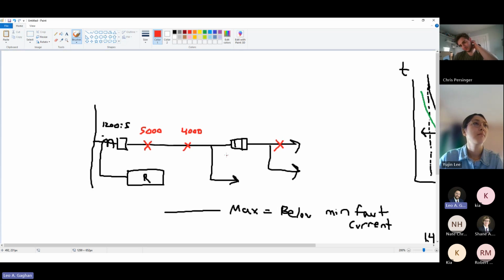So what we can do is not coordinate like we talked about before, but we can actually make this guy faster than the fuse. So when that fault happens, this device will clear that fault and the fuse will be saved. So we'll have that fast curve that's faster than the fuse. And then we can have a slow curve so that if it is a permanent fault, we can swap to that slow curve. The fuse can clear it because the fuse has to clear it because it's a permanent fault. And the fuse will operate if these people lose power, but we can continue to serve power to these people over here. It's the concept between that fuse saving and a fast and slow curve.